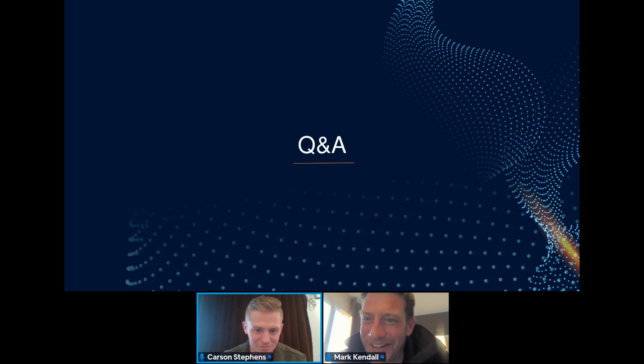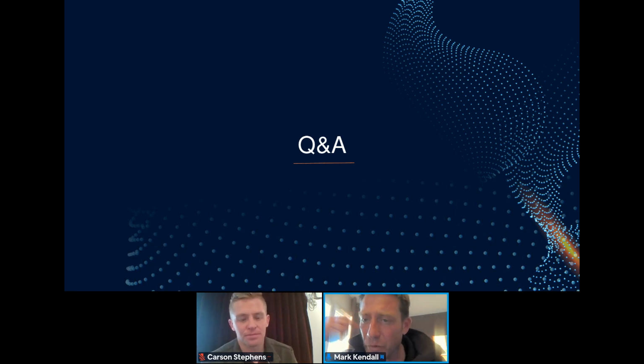Sorry. There were a couple from David that sprung out to me. So one is around avoiding leakage after discharge that could short out or erroneously damage other modules, and around the heat capacity of Fike Blue and what characteristics make it superior to water. And I want to answer those two at the same time. So the heat capacity of Fike Blue is four times that of water. Ultimately, it's well above what we see with water. And also, one of the other characteristics that make it unique is it's also a lot less conductive.